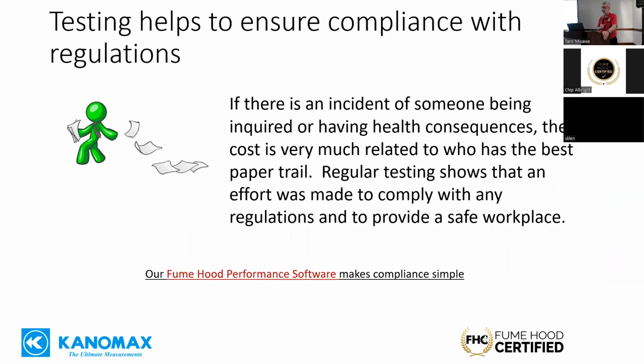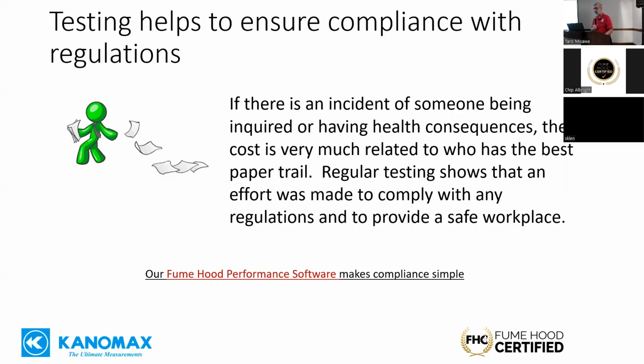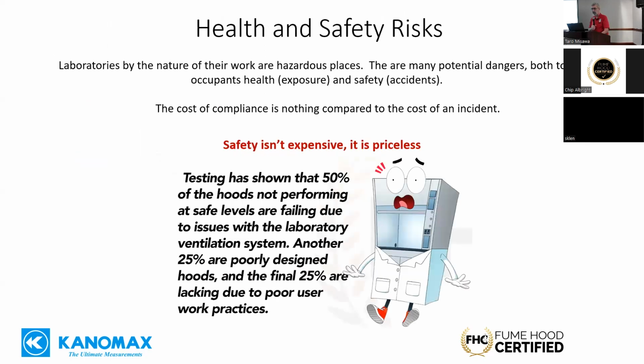Testing helps to ensure compliance with regulations. And if there is an incident, we hope there isn't, but if there is, it's going to come down to a paper trail: who can show that they did the things they needed to do so that the users were safe. We have a software solution as well, called Fume Hood Performance Software. It creates a tracking record for every hood, so we can put all the test data there and organize anything and everything pertaining to that hood in a central place where it's easy to find. So should you have an event a year from now, 5 years from now, or 10 years from now, you can go back to the software and show what we did and when we did it. It's a really good way to reduce your liability.